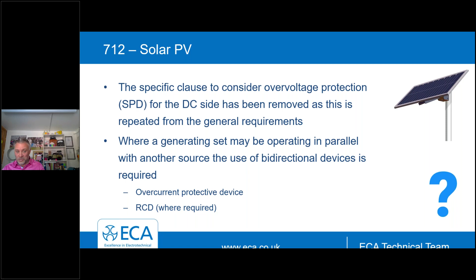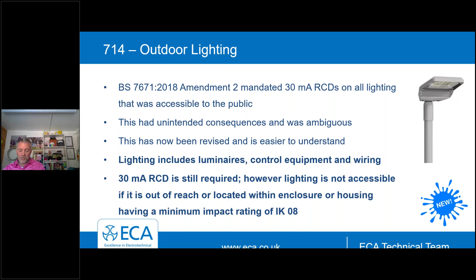Outdoor lighting. Amendment 2 brought around a lot of engineering challenges with outdoor lighting, especially in car parks, long circuits, runway, tunnel lighting, and it's just due to the capacitive effects of really, really long circuits. Some lighting circuits are easily a kilometre long, and an RCD would disconnect or trip on a perfectly sound electrical circuit. So all the examples now have been removed, the regulation has been shortened, and a new note to omit RCD protection if the live conductors or equipment are either out of reach or locked in a secure enclosure of impact rating no less than IK08. So that's a most welcome change. It'd be great to hear your thoughts on that one.